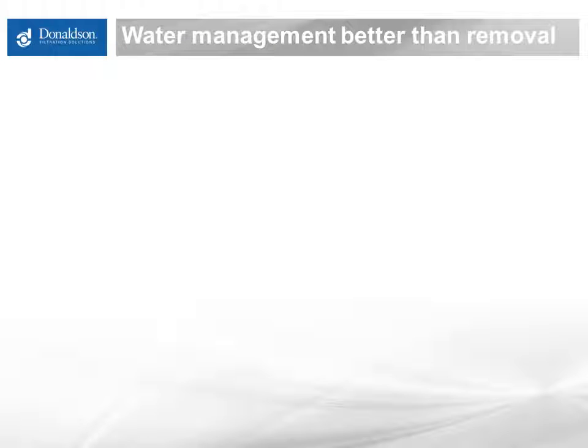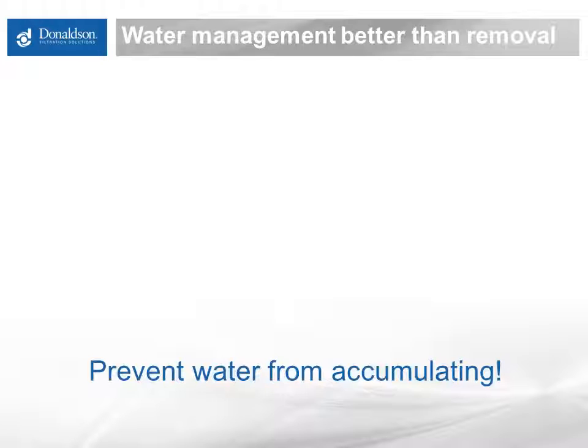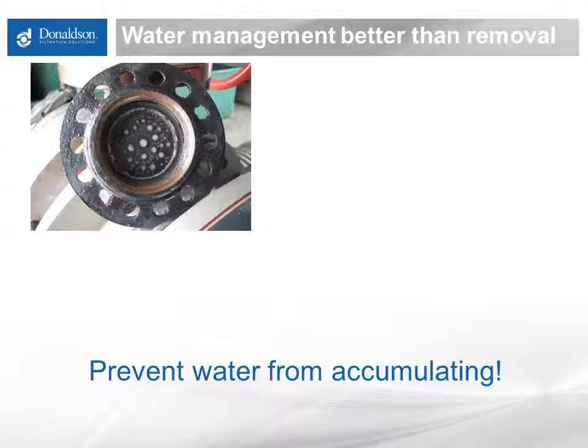Water management is better than trying to do water removal in these mobile situations. Allowing it to build up there, it just gets stirred into the fuel every time it gets moved. So the best way to prevent it from accumulating in tanks is to not have any space for condensation to occur. Many people think in the winter there probably aren't any moisture issues because the air is very dry and you just don't think of water as an issue in the winter.